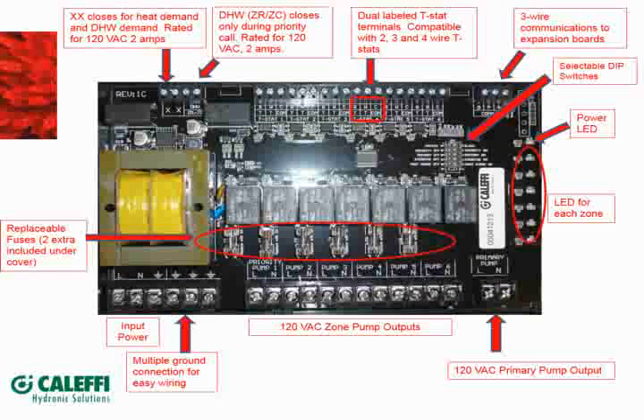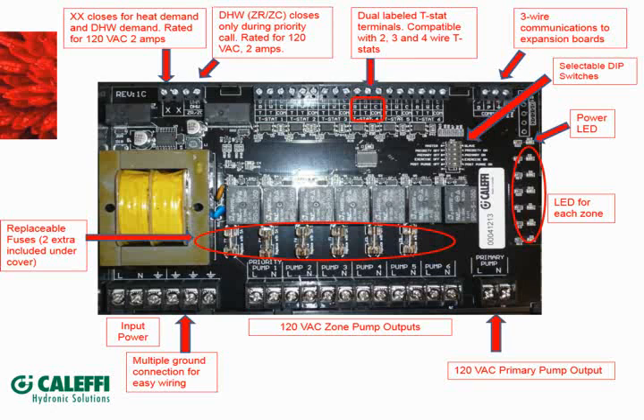So if you have some of the newer boilers, modcon boilers, they're just using 24 volts there, but some of the older oil-fired units with a reset curve, you know, they'll have a ZR, ZC, which is 120. So you are able to switch that, and you are able to fit a 14-gauge wire into there as well. Yeah, again, about those mixed voltages there, but that did pass the approval, so it's not something we came up with. That's right. Yeah, it's approved by, like I said, approved by ETL. Yeah. Again, the thermostat connection area is common among all of our controls, so they're dual labeled.